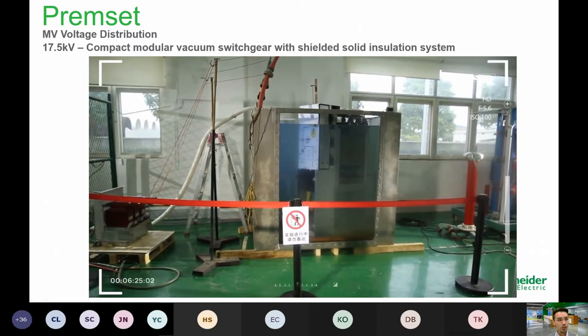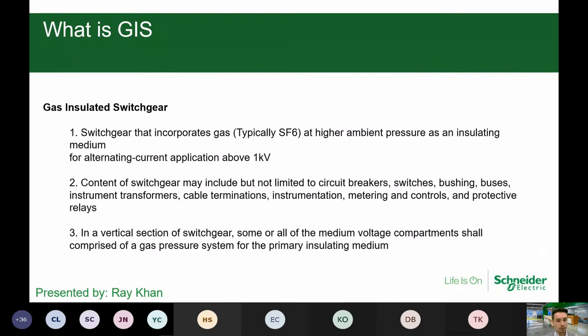Next, I will go into gas insulated switchgear. So what is a gas insulated switchgear? Generally the points are written here. It is switchgear that incorporates gas, typically SF6, at a higher ambient pressure, used as an insulating medium for alternating current above 1 kV. The switchgear comprises the circuit breaker, switch, bushing, buses, instruments, and also the cable terminations, all of these basic requirements.